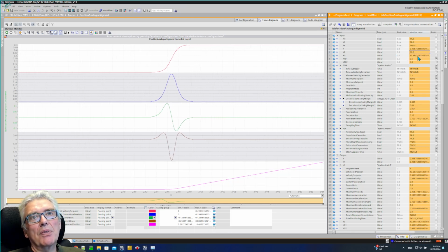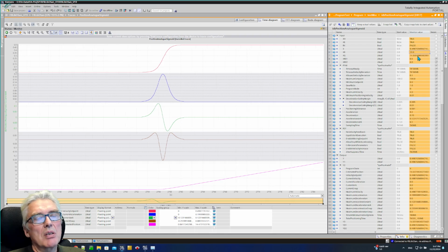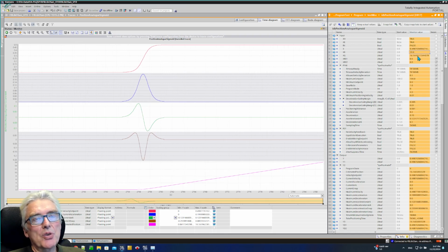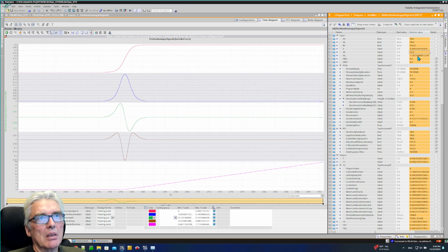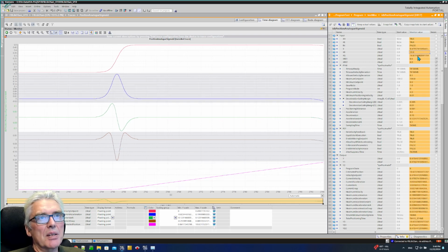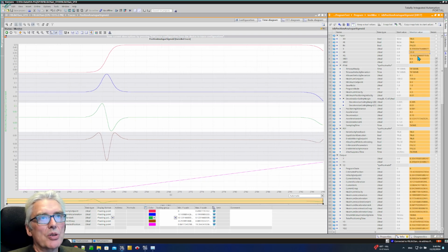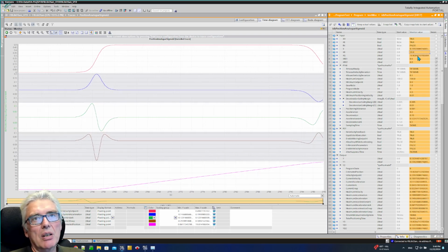Then I should pass 15. That was my original one. The 10 it didn't care about. It didn't change that set point at all, but it should run to 20. So I can increase it.